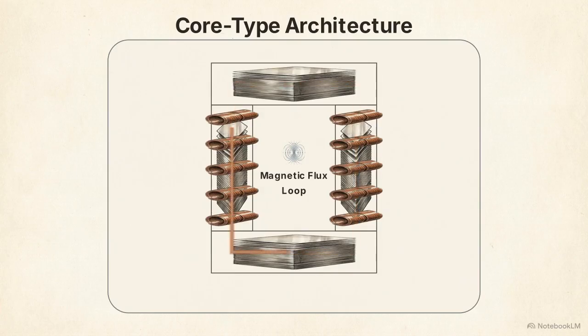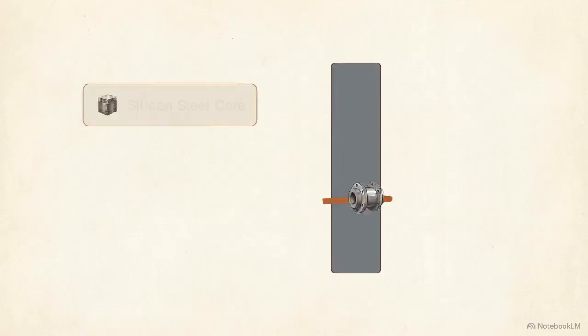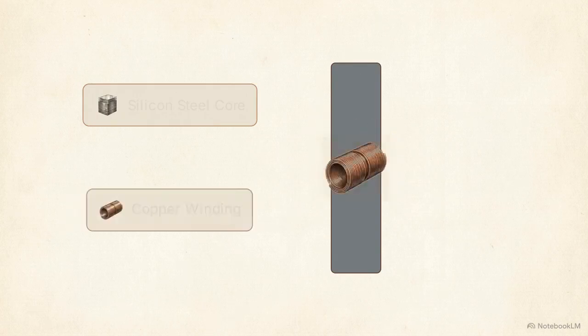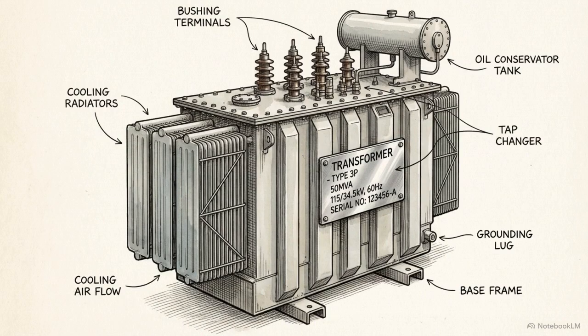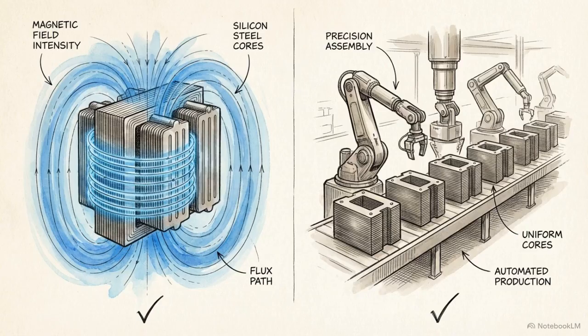The primary mechanical benefit of the core-type layout is factory efficiency. It is considerably easier to mechanically wind the copper coils directly onto the accessible core legs. Because of this manufacturing advantage, this specific topology is the globally dominant paradigm, serving as the standard for major manufacturers like ABB. Core-type architecture perfectly balances electromagnetic efficiency with a streamlined, highly repeatable assembly process.